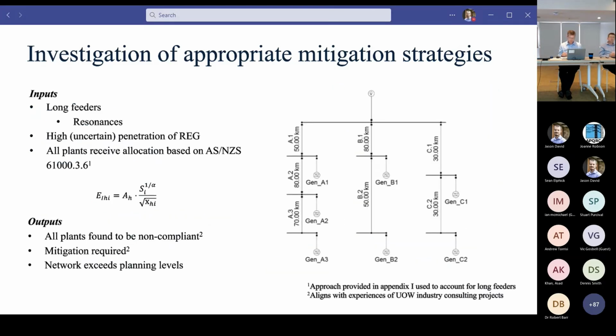in real world conditions. Moving on to the second example, in which we've got a distribution system, which we've seen a few times now, with a number of long feeders, and generators connecting throughout the network. We find ultimately if we use commonly applied modeling and data from inverter manufacturers, that all generators are non-compliant. We find that all generators require a level of mitigation and that the network will exceed its planning levels.